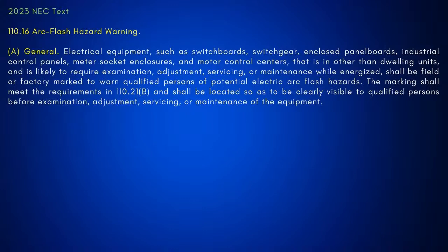One of the things I think is a little bit of an anomaly here is one of the questions that somebody asked us: does NFPA 70E apply to a residential project, a dwelling unit project that you're working on? 70E applies to anything if you're working on it while it's energized. Well, no, I'm just saying that you don't have to put the warning label on there, because it's other than dwelling. That's right. But 70E would still apply because what? A workplace. That's right, because you're working on it energized.